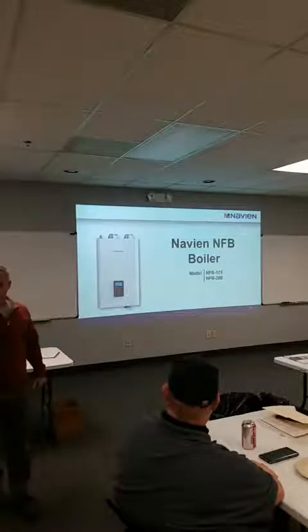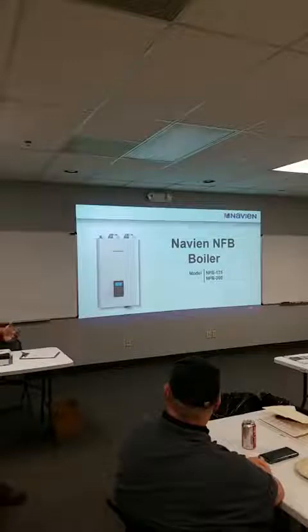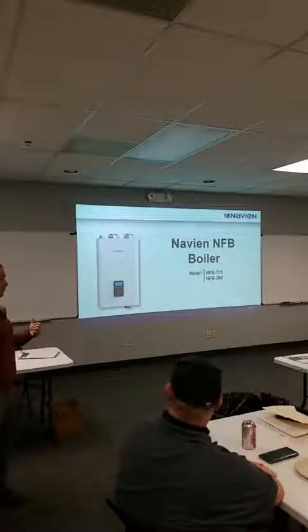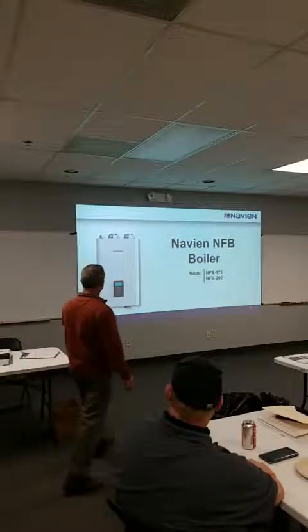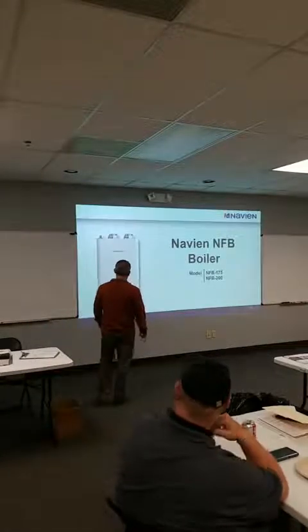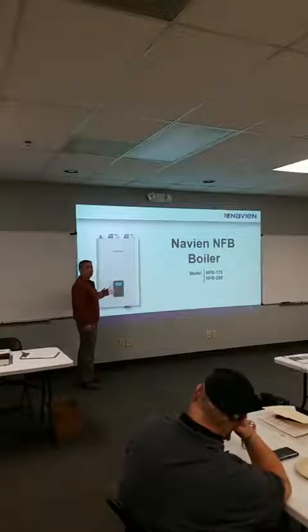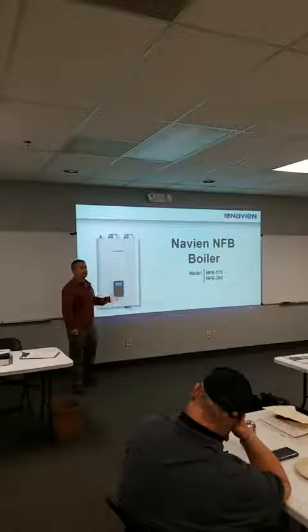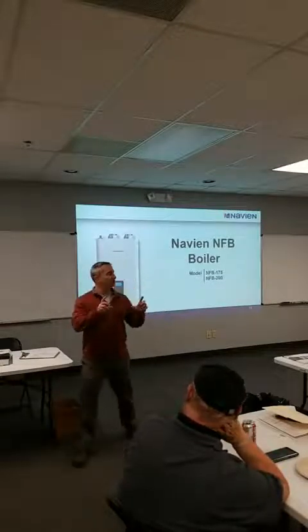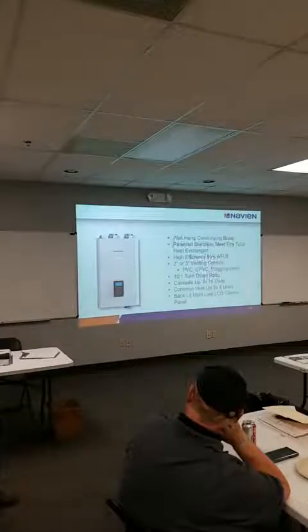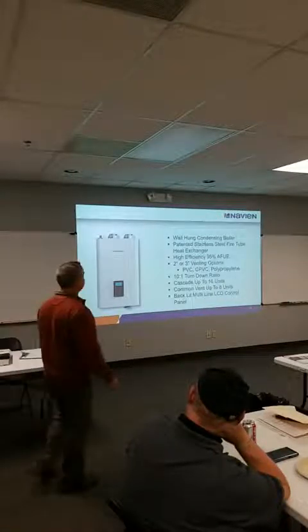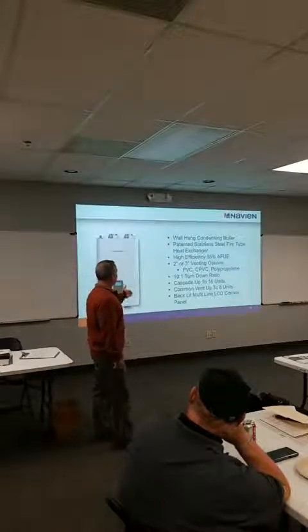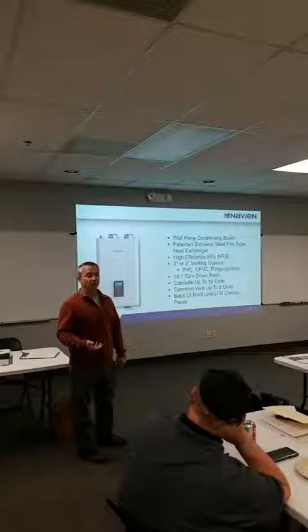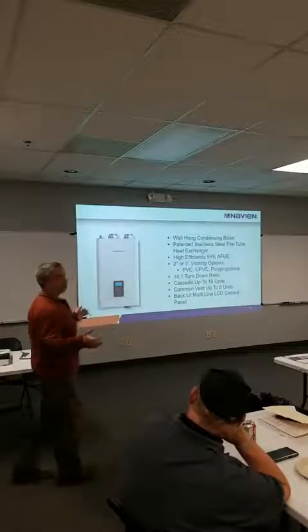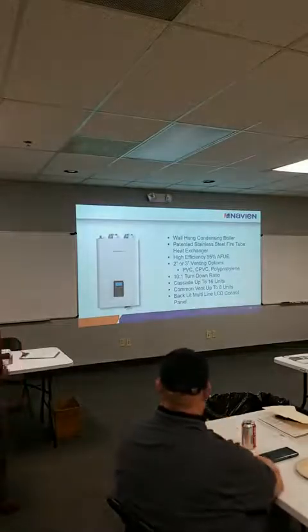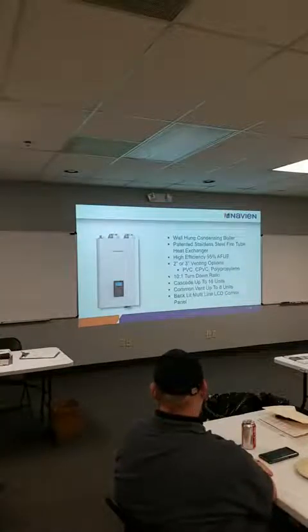The NFB we came out with last year, or I guess 2019, NFB, Navien fire tube boiler. It has our fire tube heat exchanger in it. Looks basically the same. It has the new keypad on it. This keypad is going to be in all of our new boiler equipment and on the combis, except for the commercial boiler, which is going to have that big touchscreen on it. Some of this stuff is going to change this year, but again, you saw this page. We're taking the turn down ratio on this boiler up to 15:1 this year. We're extending out the venting to 65 feet on 2-inch. The cascade and communication are the same.